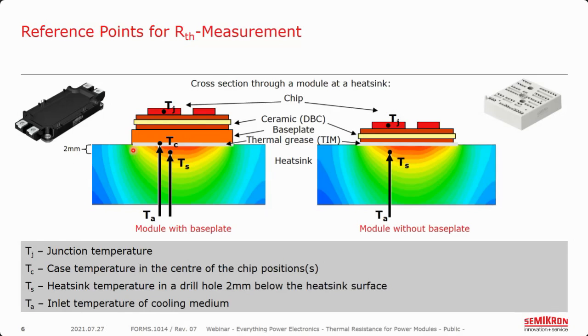If we drilled another hole from the bottom but stopped within 2 millimeters from the surface of the heat sink, we would have the heat sink, or sink, temperature T sub S. We then have the heat sink itself and the temperature of the coolant flowing across it — usually air or a water-ethylene glycol mix. We refer to the temperature of this coolant as it enters the heat sink prior to being heated as the ambient temperature, T sub A.